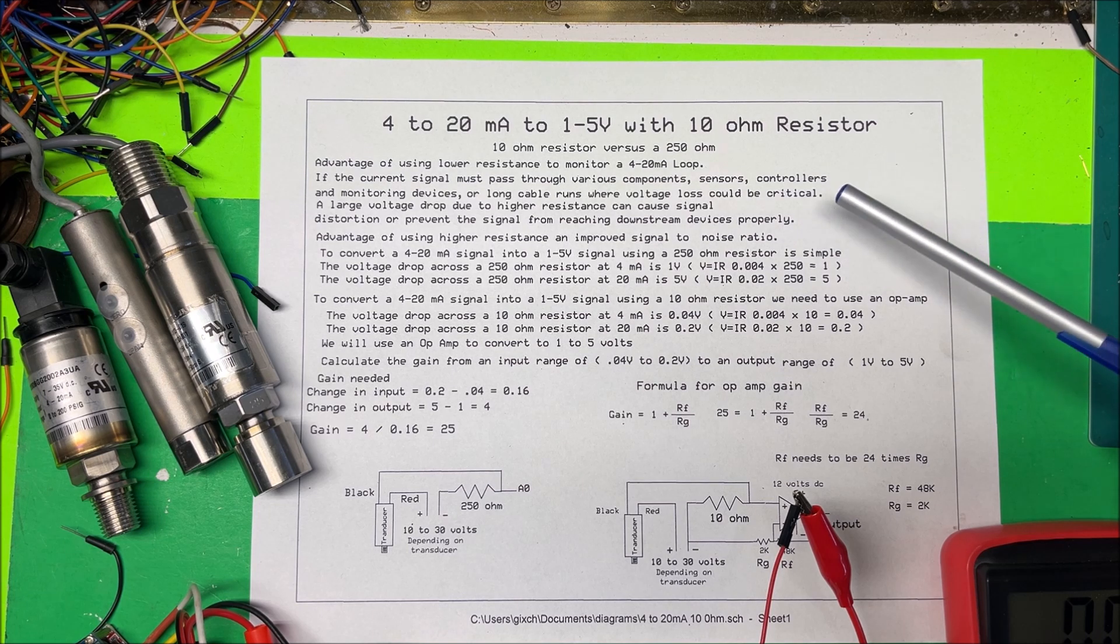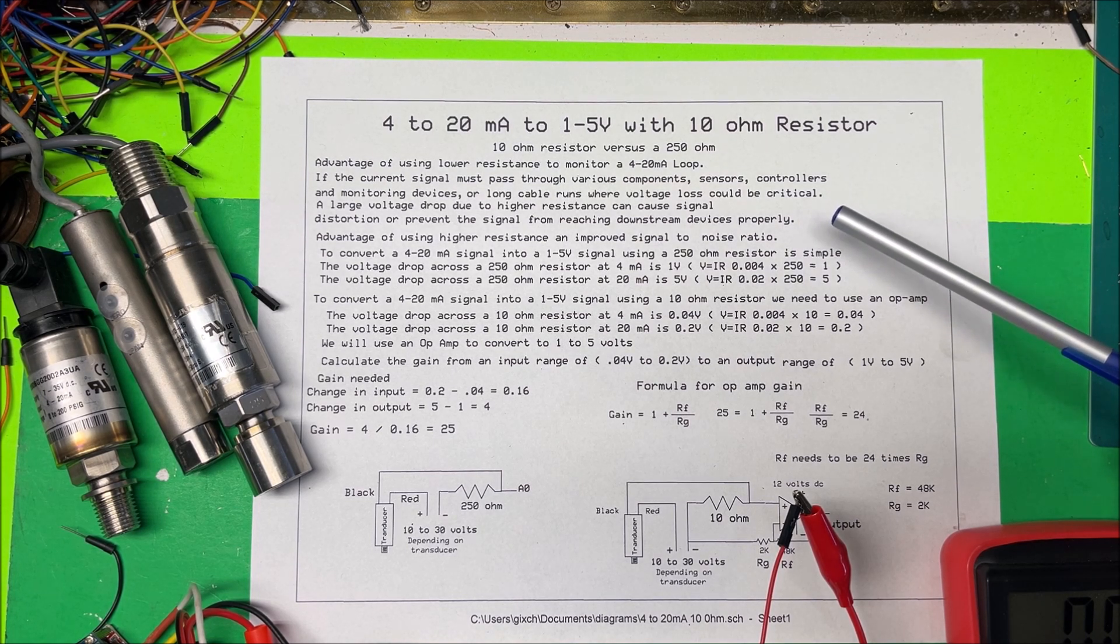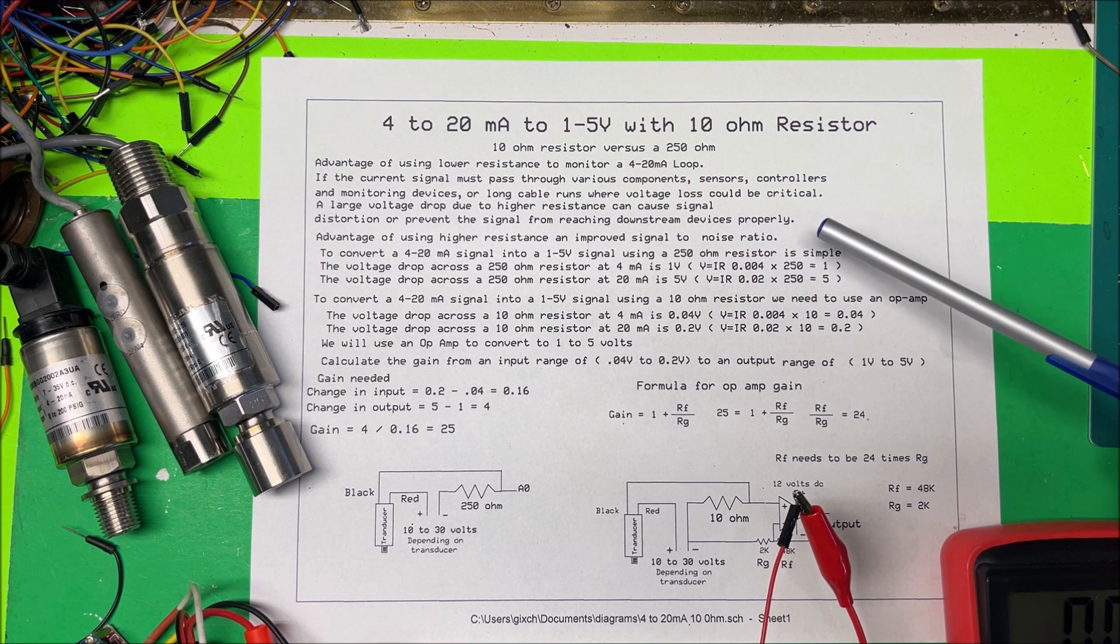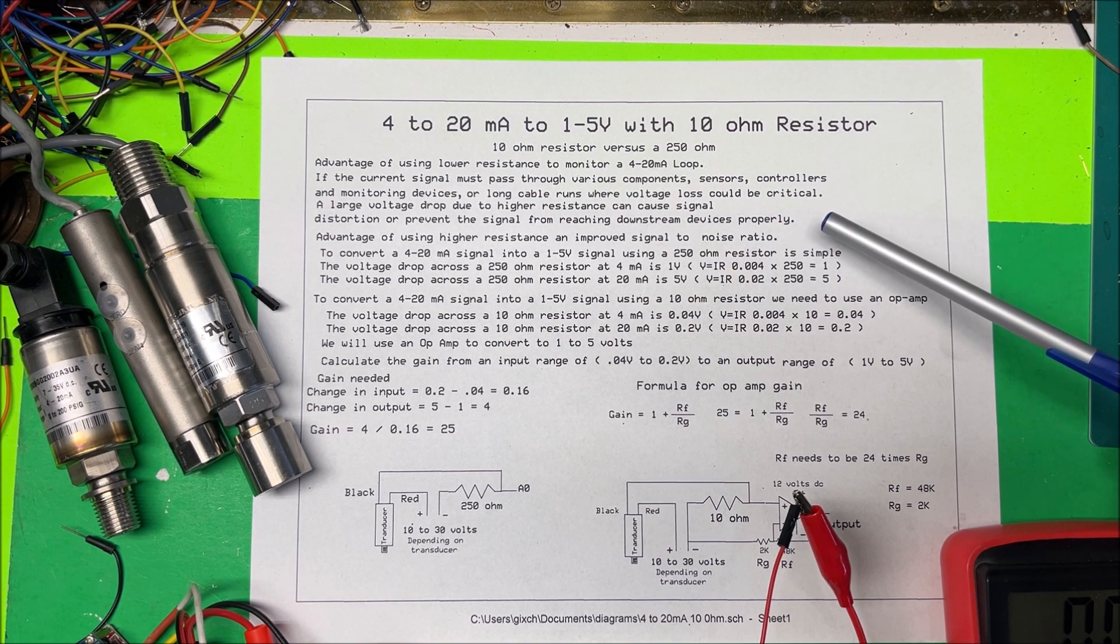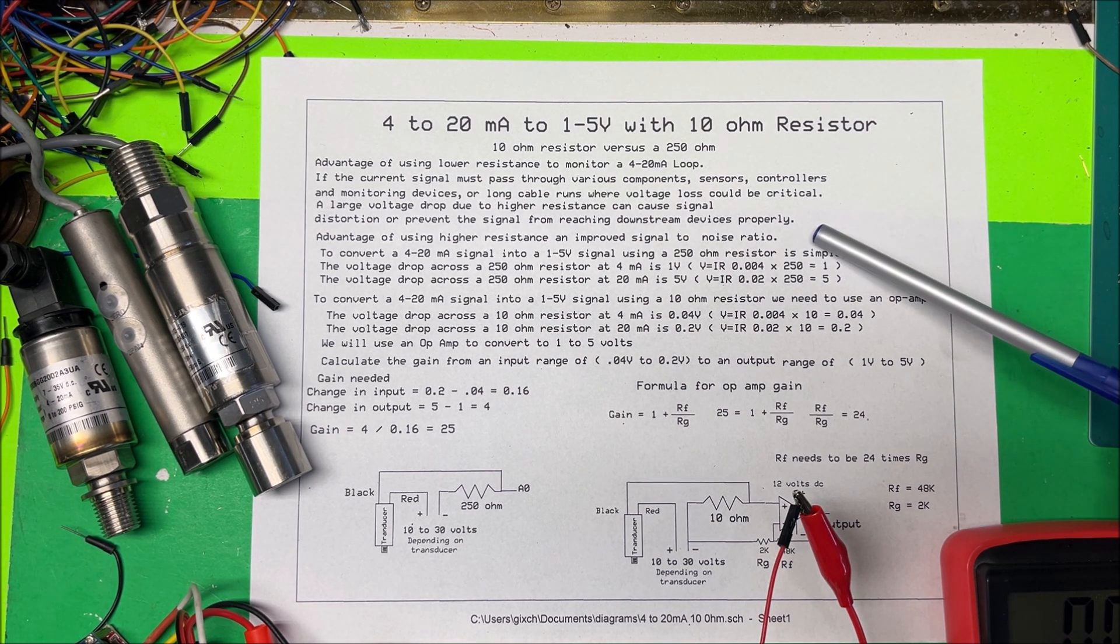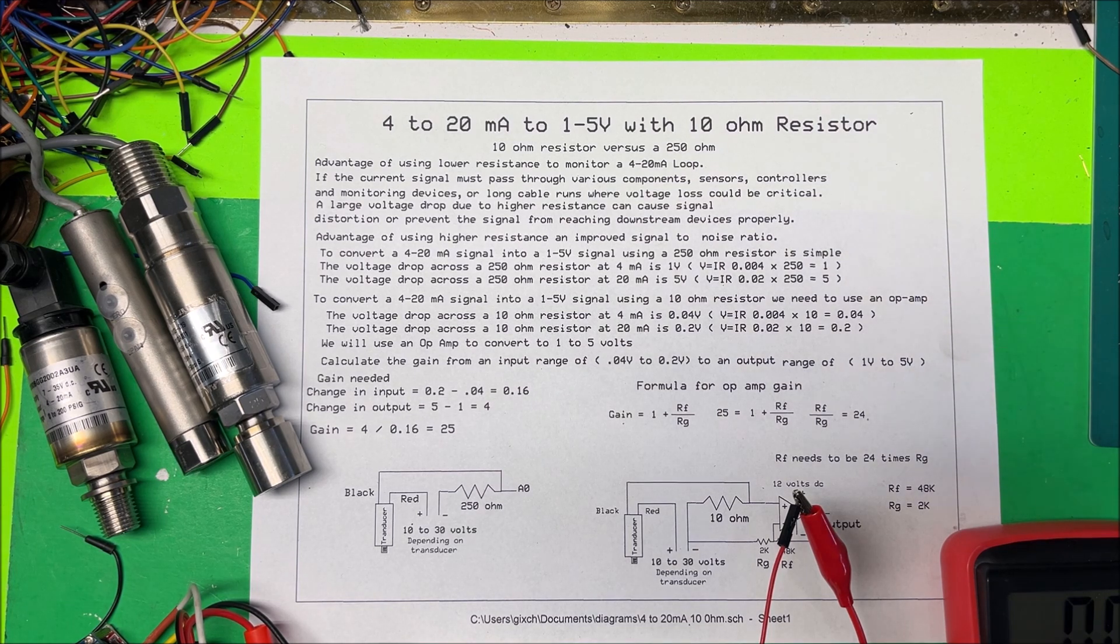Now if you can, it's better off to use the 250 ohms because it has higher resistance and it's going to improve the signal to noise ratio. But if you have to, we can use the 10 ohm resistor.